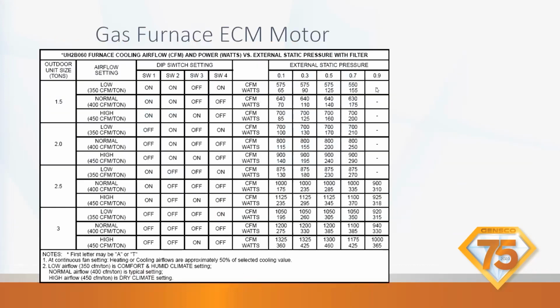How about with an ECM motor? So we're going to go to the ECM motor, and you'll notice that the volumes of CFM are pretty much the same across the board. So we're going to take our static pressure just to make sure we're not above 0.9. If we're above 0.9 on this furnace, it's not going to maintain your pressure or your CFM. You see where it starts to drop off at 0.9? It's already down to 900 CFM on the 2.5-ton normal. If you look at the 1,000, 900. So it's already starting to drop off at 0.9. If you go to 1.0, we're probably going to be down to 850, 800 CFMs per ton, instead of where we want it.